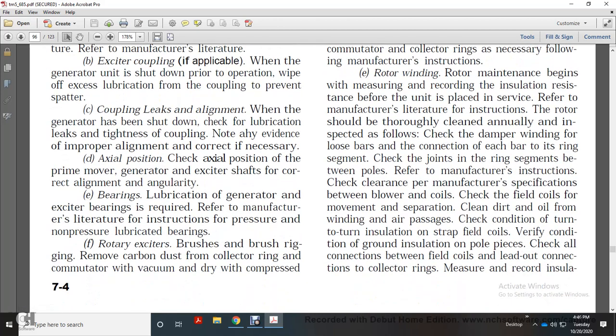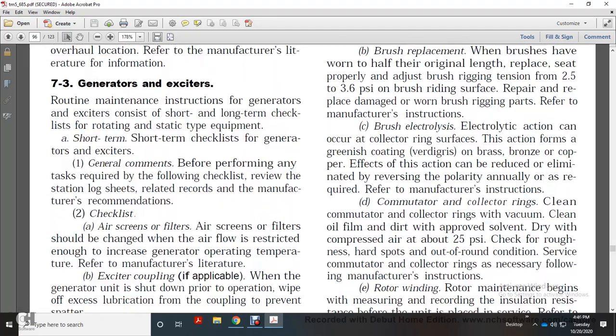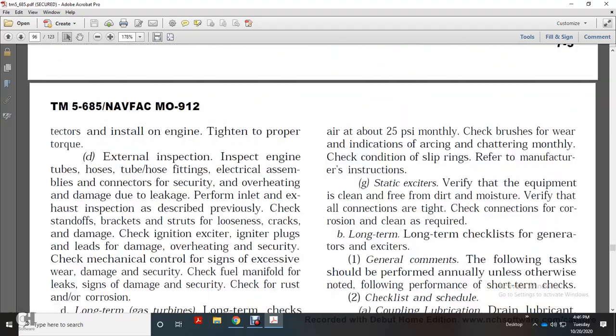Rotary exciters, brushes, and brush rigging: remove the carbon dust from the collector ring and the commutator with a vacuum and dry with compressed air at about 25 psi. Monthly, check the brush for wear, indicating arcing and chattering, and monthly add slip ring lubricant, referring to manufacturer instruction. Static exciter: verify the equipment is clean and free of dirt and moisture, and verify that all the connections are tight. Check the connection for corrosion and clean as required.